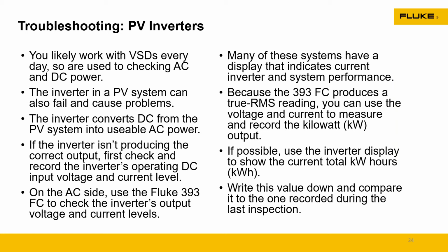This is where you would use some type of power quality unit. You could validate that and monitor it, because it may not be happening during the time that you were checking it. You would have to go out and do a load study on it to see what was happening with it. But the inverters are smart. They typically will give an indication of what happened to cause it to trip.